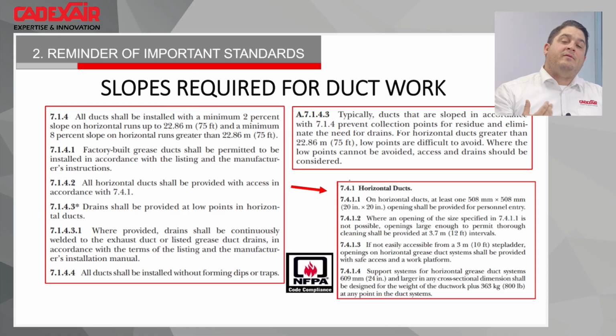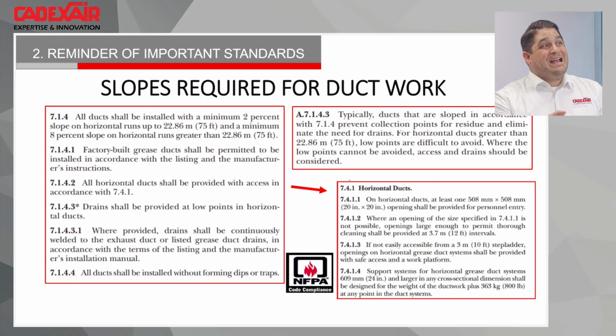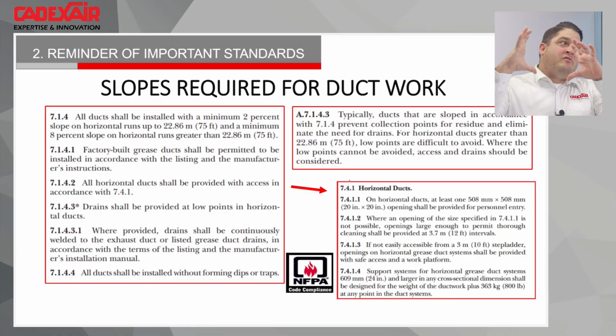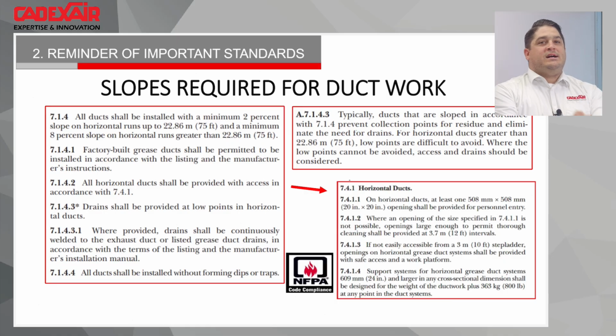But the beauty is that they put in this new regulation: now you can put a drain inside of the ductwork. Where you have two slopes going together, you will put a welded drain and also an access door to be able to clean it. And you need to put a ball valve to be able to drain it. And while you have an access door, it's sure it will clog one day.